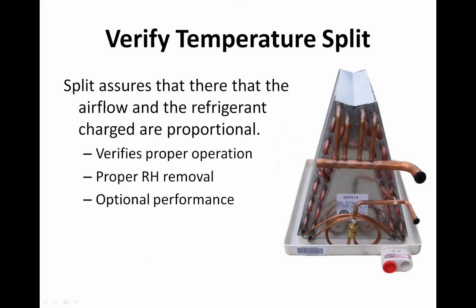Now, the last thing I want to talk a little bit about is temperature split. And we talked a little bit earlier about airflow. Back when I first started in this industry, my dad would tell me, just charge it to the correct superheat, get the target superheat, and then go back in the house and set the airflow by getting the split right. Get about a 20-degree drop across the coil. That's good, okay? And split, we typically think about split. What it is, it assures that the airflow and the refrigerant charge are proportional. It assures that basically we have the right amount of refrigerant in the system for the airflow that we have. And it verifies proper operation of the coil. It verifies proper relative humidity removal and optimal performance.